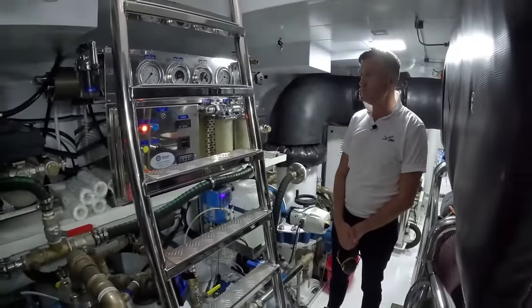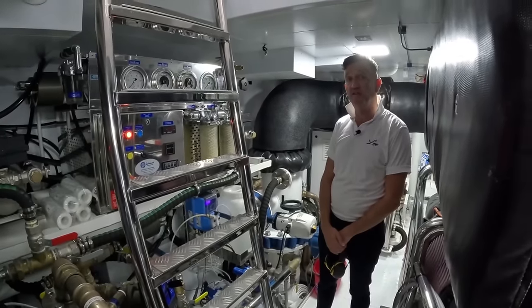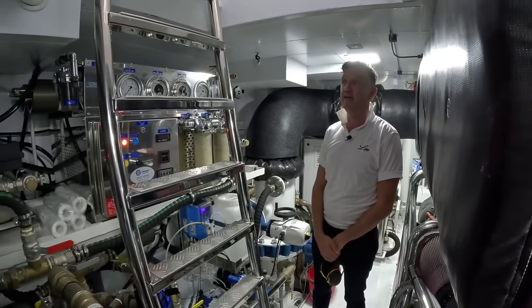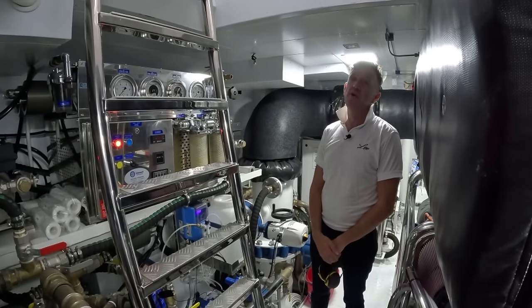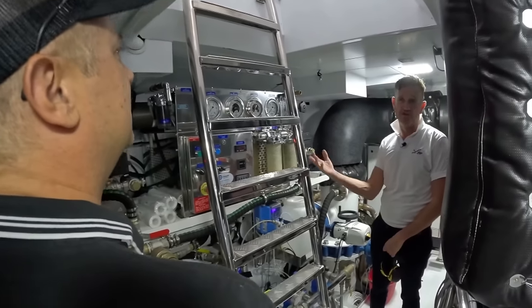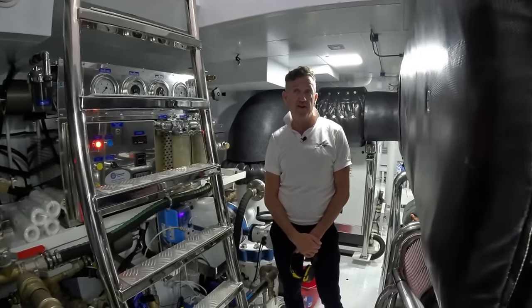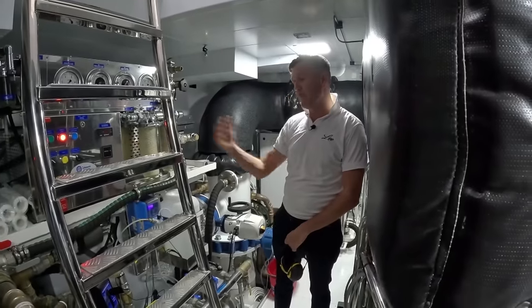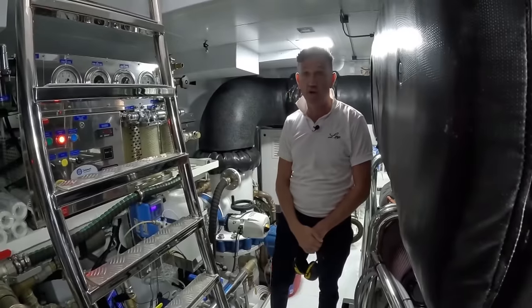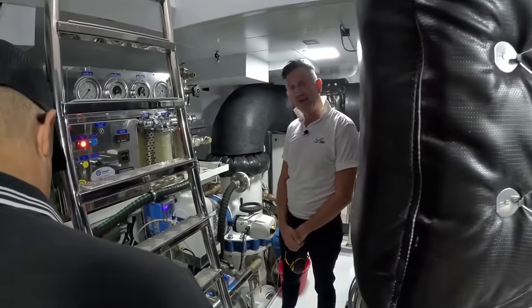What's your average daily water consumption? Sometimes we can do 10 tons — 10,000 liters. If you've got 10 guests on board with 10 crew, when you've got children in the swimming pools with suntan cream, the water goes green and you're dumping it on a daily basis — that alone is about six tons. So it's high consumption. I'm forever changing the filters and back-flushing. It's super imperative that you keep this kit in tip-top condition at all times.